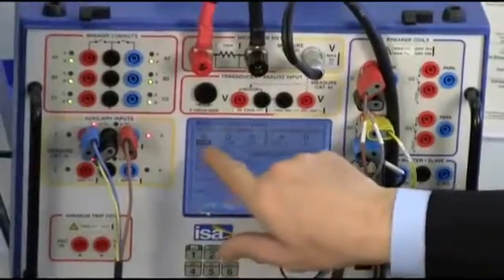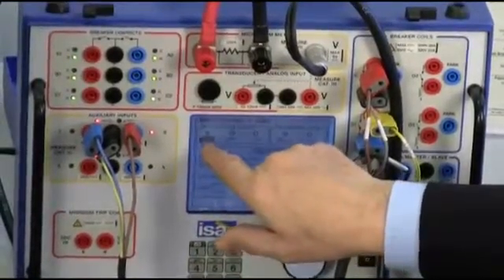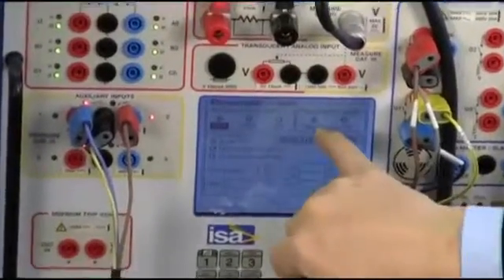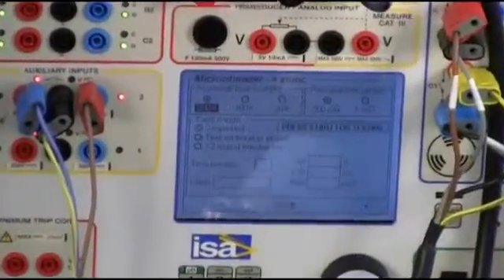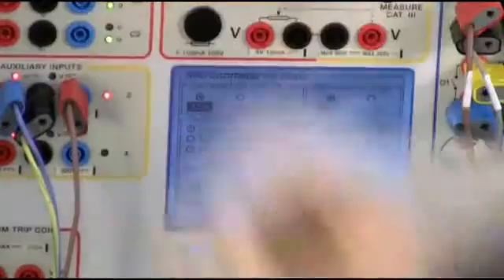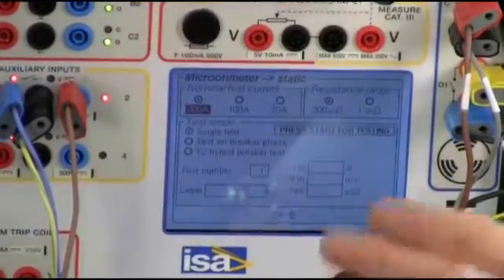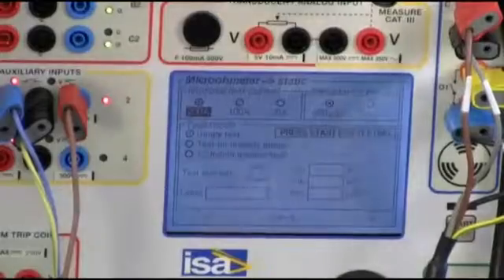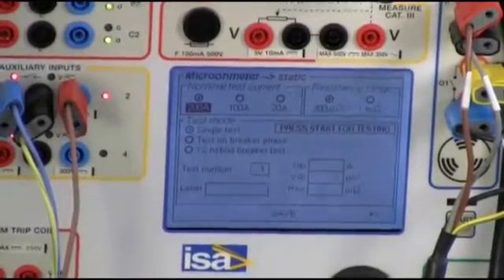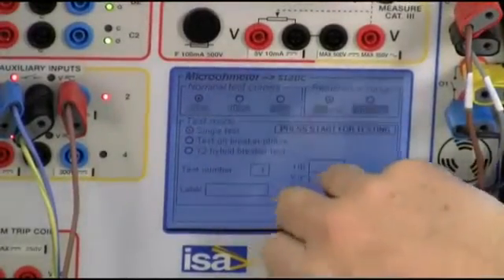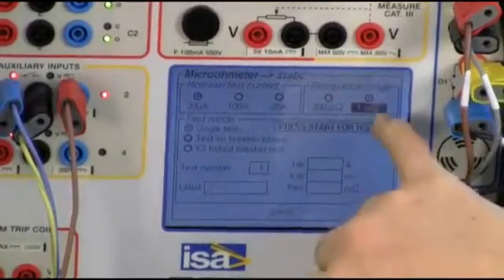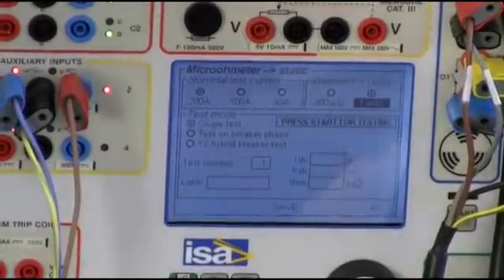For instance, the first setting that you have here is the current for the test and the resistance range. Now, I know by the manufacturer that the resistance, the nominal resistance value is in the range of half a milliohm. So I select 200 amps, but here I have to select one milliohm.